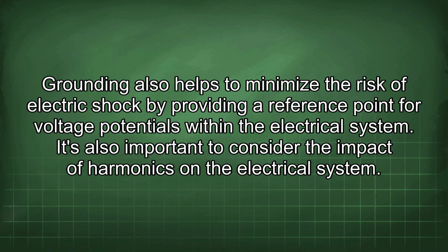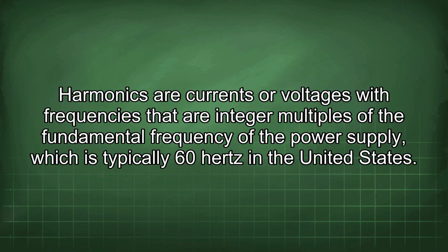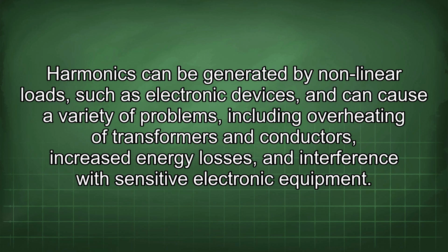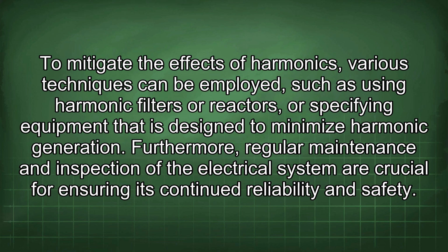It's also important to consider the impact of harmonics on the electrical system. Harmonics are currents or voltages with frequencies that are integer multiples of the fundamental frequency of the power supply, which is typically 60 Hz in the United States. Harmonics can be generated by nonlinear loads such as electronic devices and can cause a variety of problems, including overheating of transformers and conductors, increased energy losses, and interference with sensitive electronic equipment. To mitigate the effects of harmonics, various techniques can be employed, such as using harmonic filters or reactors, or specifying equipment that is designed to minimize harmonic generation.